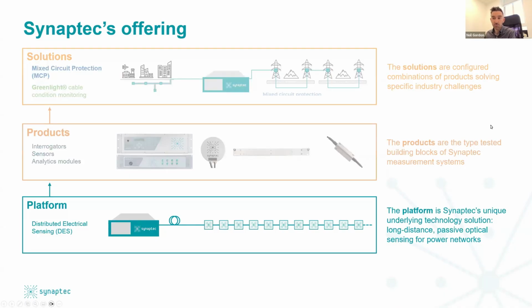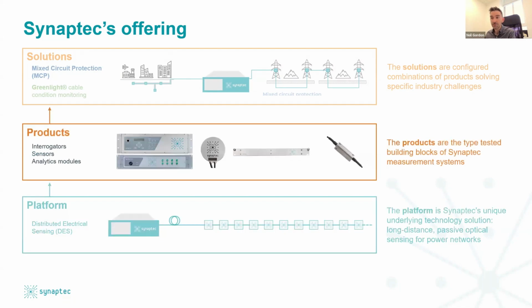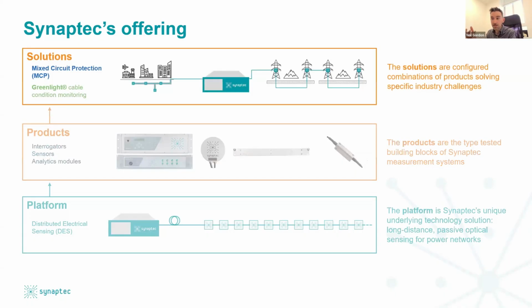So, to begin with, the platform is our patent protected unique fiber optic measurement technology, which we call distributed electrical sensing, or DES. From that platform, we build discrete products, which are the sensors themselves, the interrogation systems which monitor those sensors, and the analytics modules. These are the individually certified and type tested building blocks, which then become solutions. So the solutions are therefore the configured combinations of those products, which address those specific industry challenges.